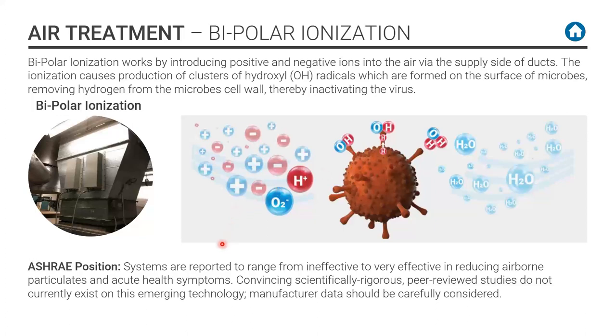Now, ASHRAE's position is very clear. It says systems are reported to range from ineffective to very effective in reducing airborne particulates and acute health symptoms. However, convincing, scientifically rigorous peer-reviewed studies do not exist currently. And we have to be careful what the manufacturers are telling us. Basically, there's a lot of studies out there. I've read at least six. Five of the six were sponsored by the manufacturers, and they talk about viruses on surfaces. They're not talking about airborne viruses. So again, it's a system that's out there, not something that we're recommending for viral control.